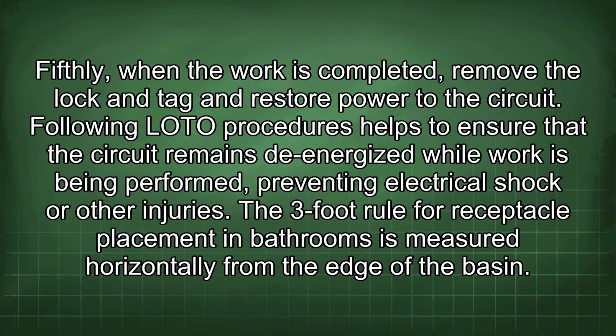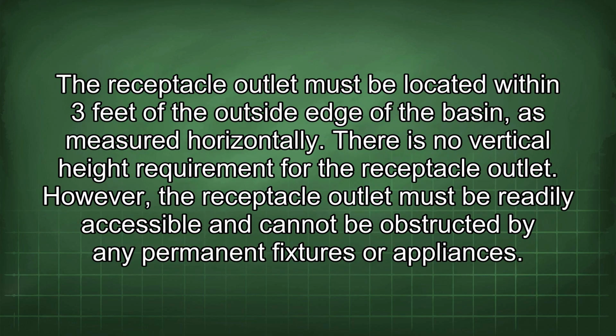The 3-foot rule for receptacle placement in bathrooms is measured horizontally from the edge of the basin. The receptacle outlet must be located within 3 feet of the outside edge of the basin, as measured horizontally. There is no vertical height requirement for the receptacle outlet. However, the receptacle outlet must be readily accessible and cannot be obstructed by any permanent fixtures or appliances.